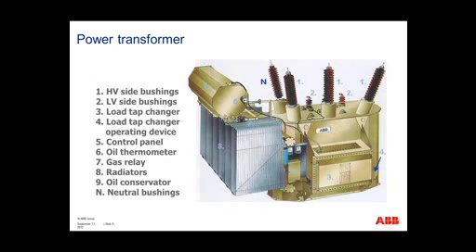Some major aspects of the transformer, the physical aspects. First and foremost, you have the core, and the core is located inside the steel structure of the transformer. The core is surrounded by oil. Oil helps keep the core cool. The cooler you can keep the core, the more power the transformer can move across the system.